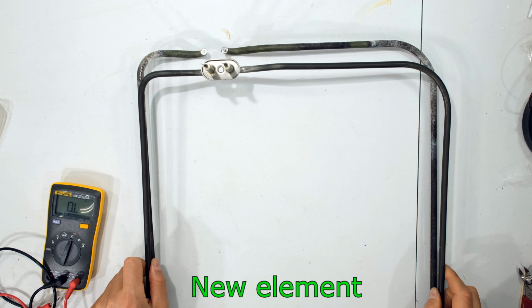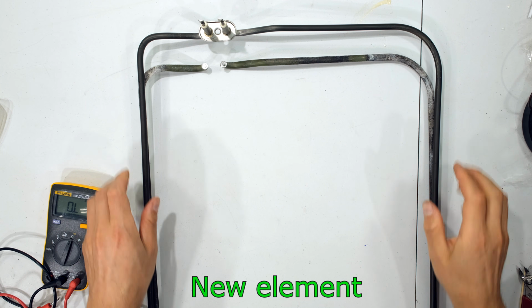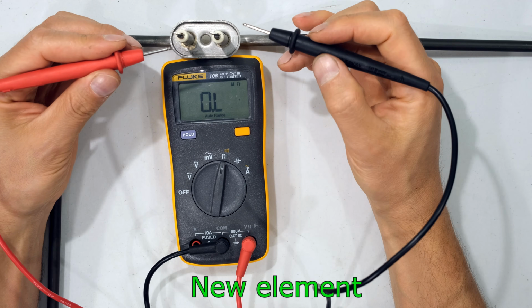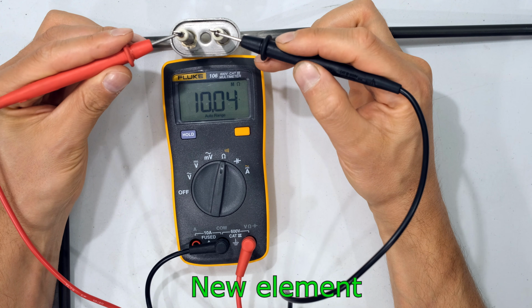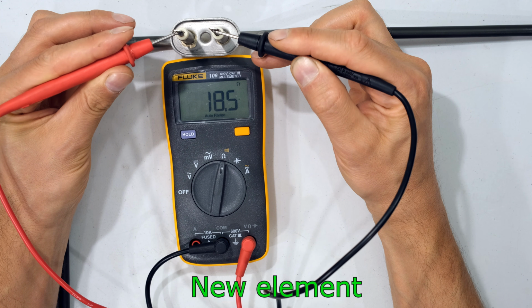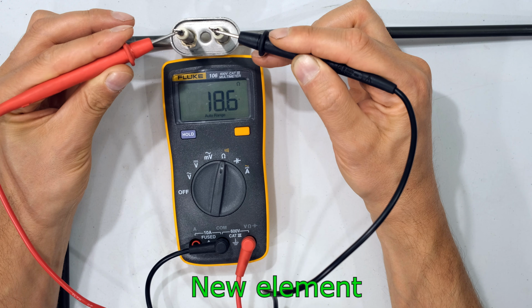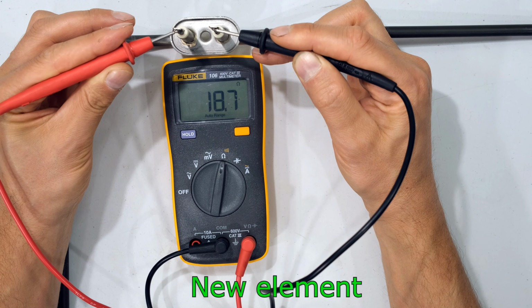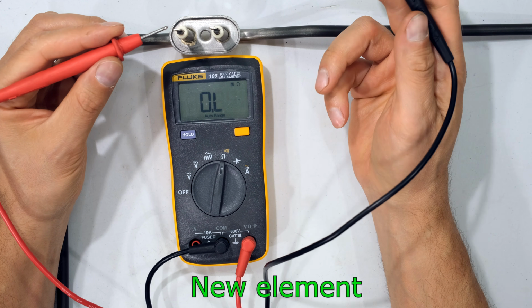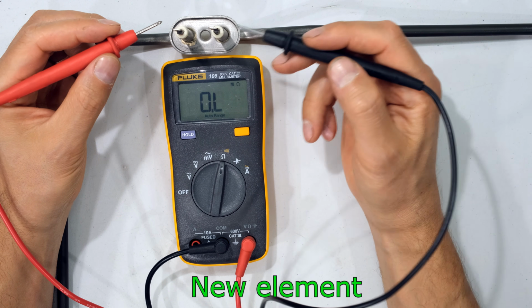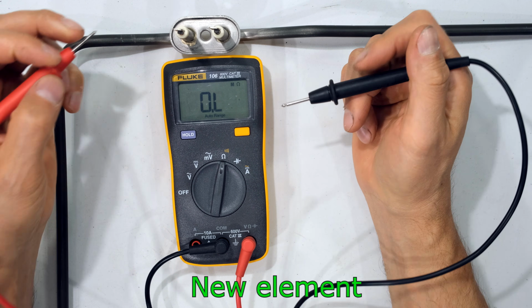So what I've done is I've got an element made in the same design, so I can use this element instead of this element. Right, and just to show you, here are the terminals for the resistor inside, and they're 18.6 or 18.7 ohms. So it is matching the other element, and that works out to be close to 2.7 kilowatts for this element.